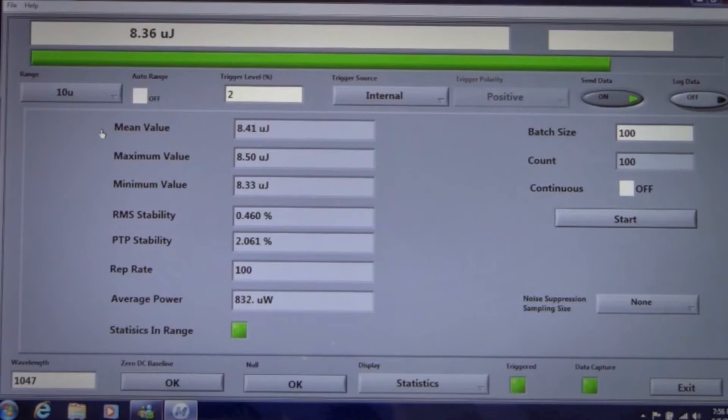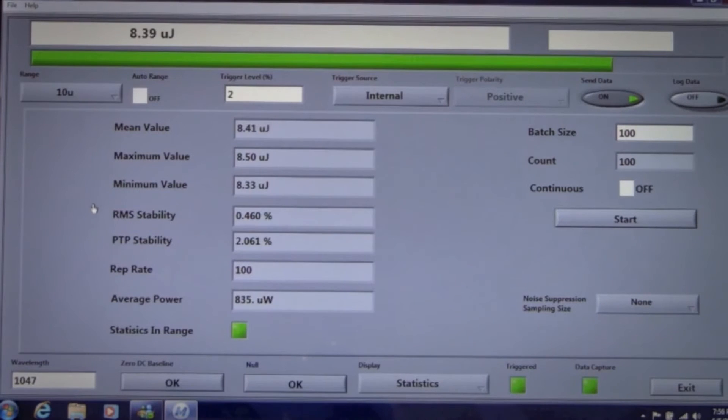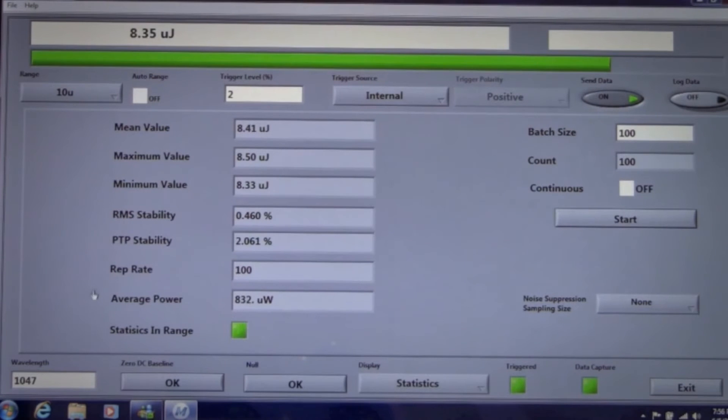We can see the mean, maximum, and minimum energy values and look at the RMS and peak-to-peak stability. We also capture the laser rep rate and calculate average power on the run.